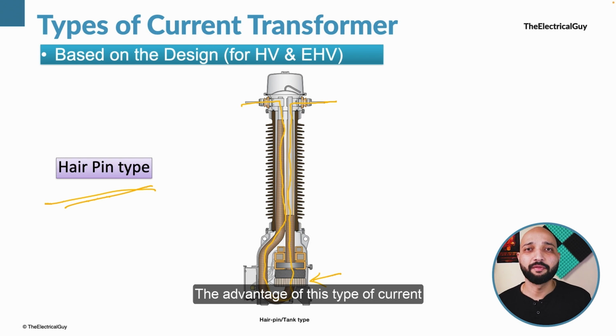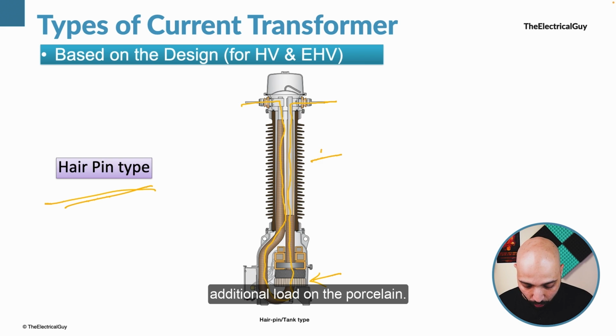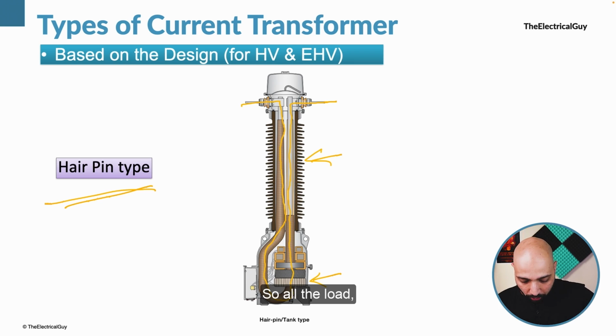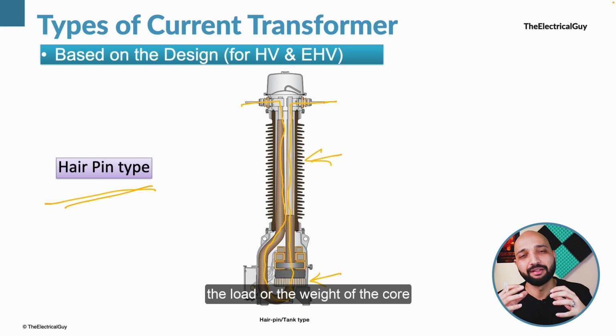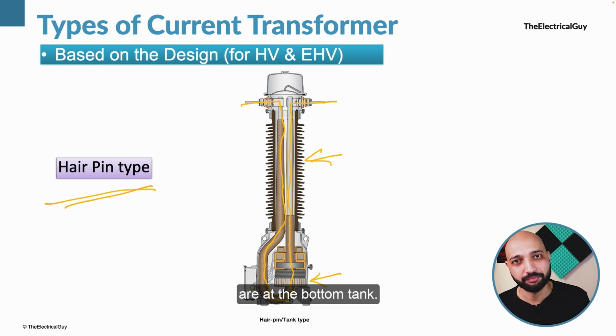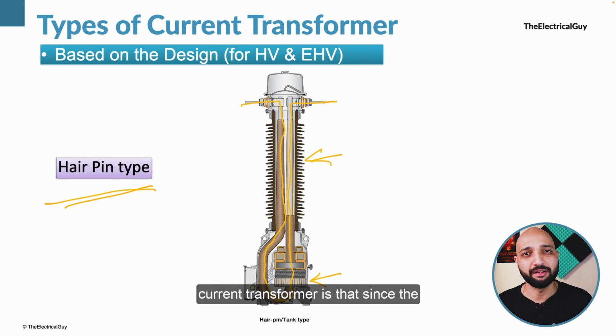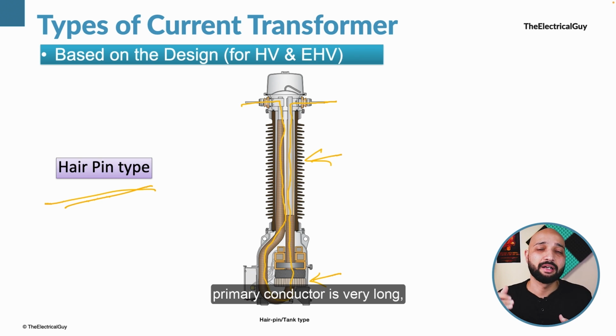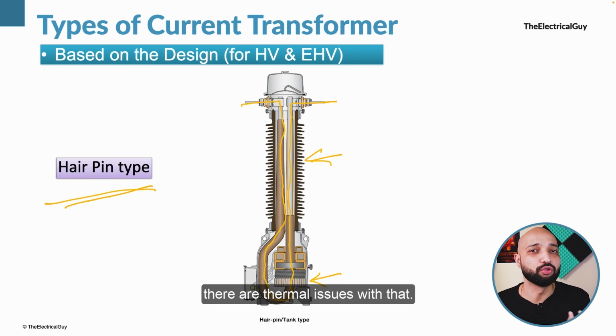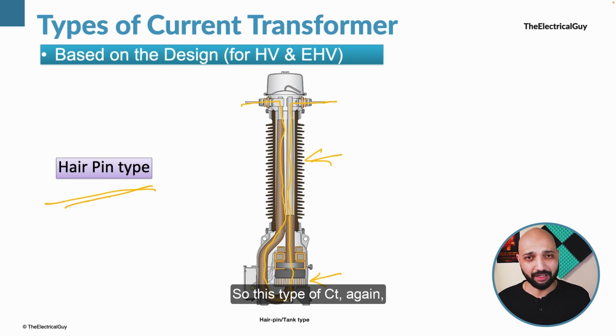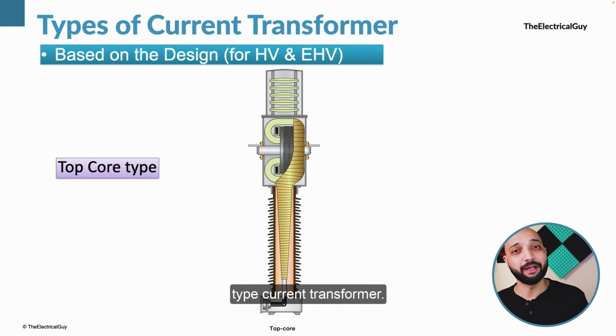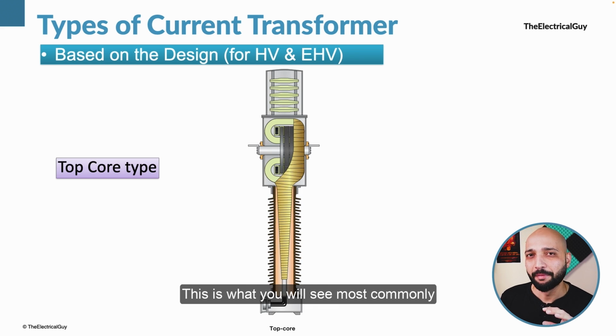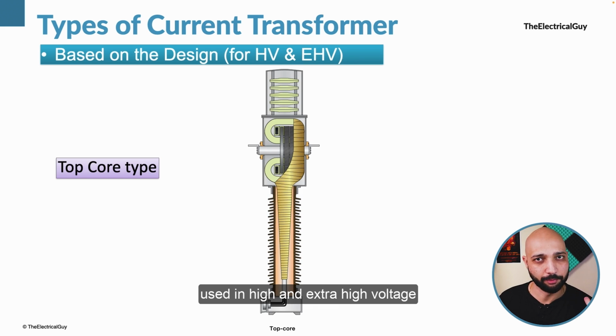The advantage of this type of current transformer is that there is no additional load on the porcelain. All the load or the weight of the cores is at the bottom tank, right? So that is the advantage that we have here. But the problem with this type of current transformer is that since the primary conductor is very long, there are thermal issues with that. So this type of CT, again, you will not find very frequently used. There is one more alternative to this, and that is called the top core type current transformer. This is what you will see most commonly used in high and extra high voltage substations.